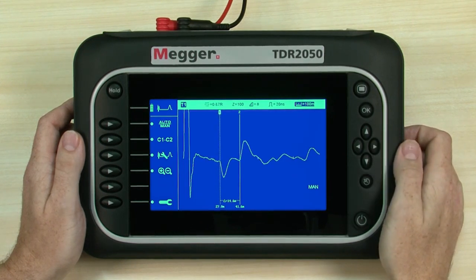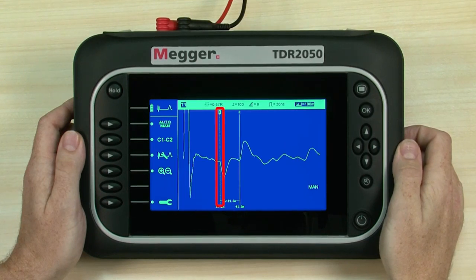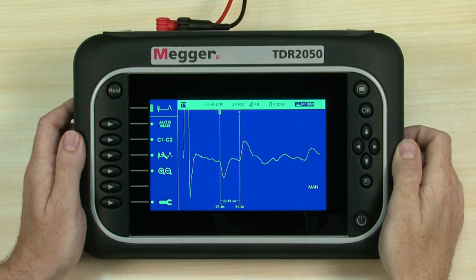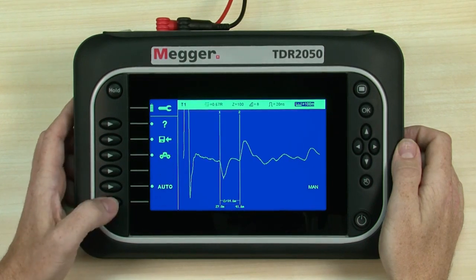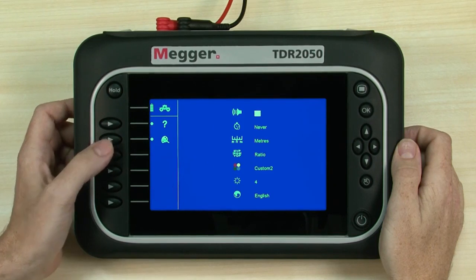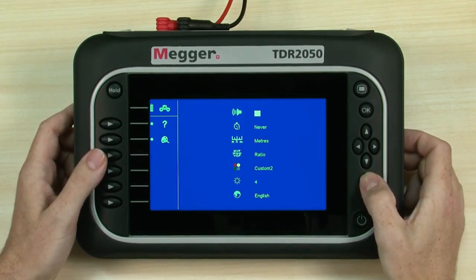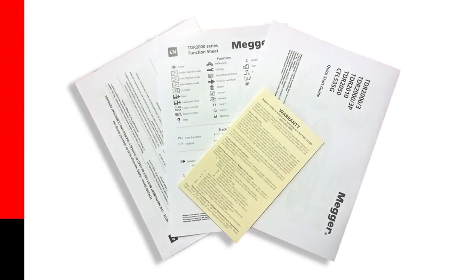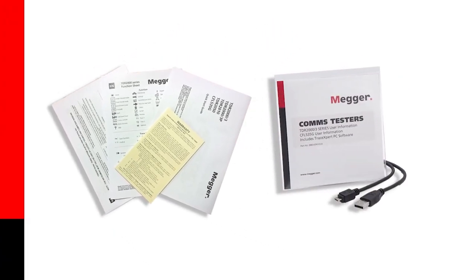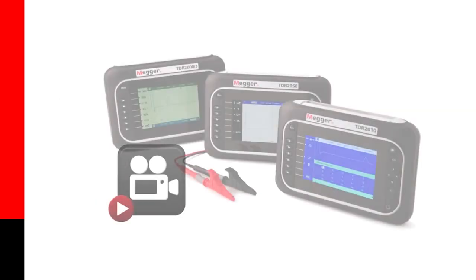Release the navigation button to stop cursor movement. We position cursor 1 at the start of the first event, and cursor 2 at the start of the second. A delta measurement shows the distance between the events. We hope that this quick introduction to TDR-2050 operation has been useful and allows you to get started on your testing and fault finding. There are some useful printed documents in the box and many more on the support CD. Watch out for other videos in this series. Thank you for watching.